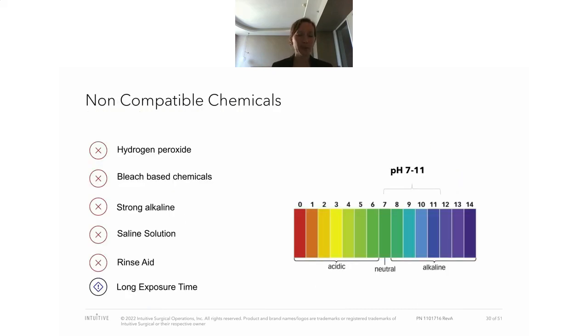So we already spoke about the chemicals and the compatibility of chemicals. I just want to highlight this once more and then also show you some pictures why this is important. I want to emphasize the recommendation for a detergent with a pH of 7 to 11 and to avoid the use of hydrogen peroxide, bleach-based chemicals, strongly alkaline chemicals, and also saline solution. I forgot to mention that this is in particular important for the OR, where quite often they have saline solution available. But saline solution, as with all the other instruments, can lead to corrosion, and that should be avoided.